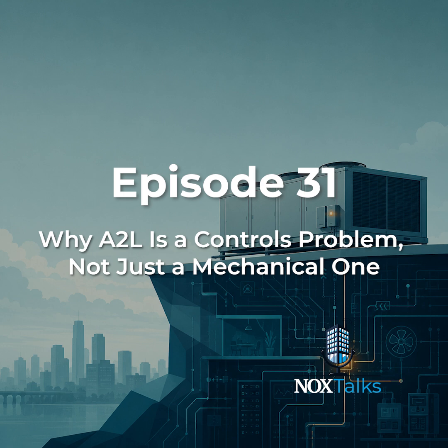So let's back up. There's a federal law called the AIM Act, the American Innovation and Manufacturing Act, and it restricts the old high global warming refrigerants, the HFCs, like the R-410A you've known for years. Now, important nuance, the AIM Act doesn't instantly ban your existing R-410A systems. They can keep running and get serviced. What it does is restrict those higher GWP refrigerants in new equipment across many HVAC and refrigeration categories.